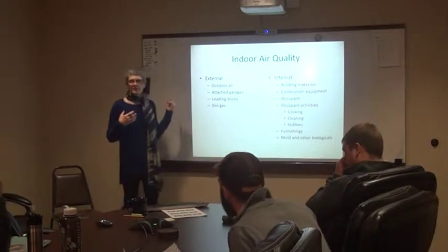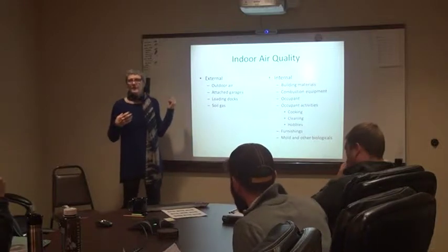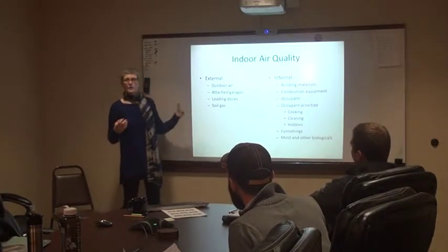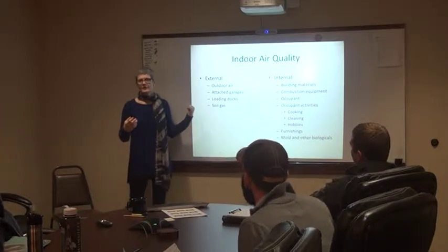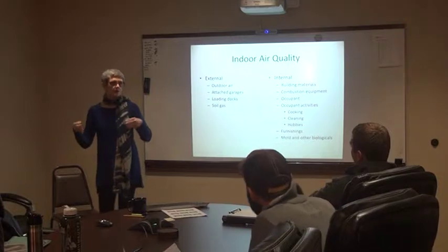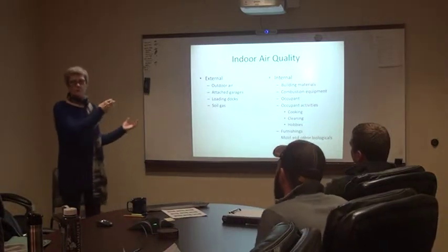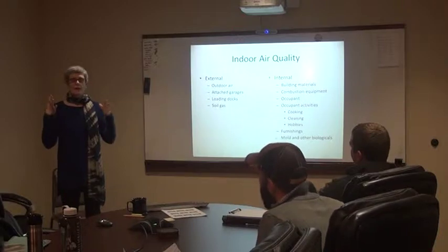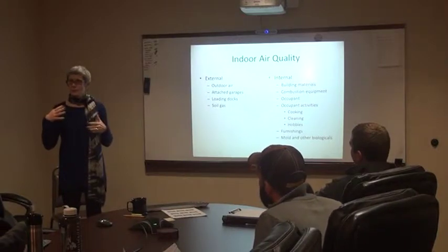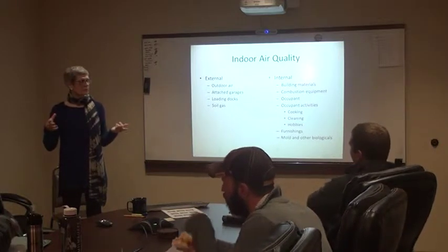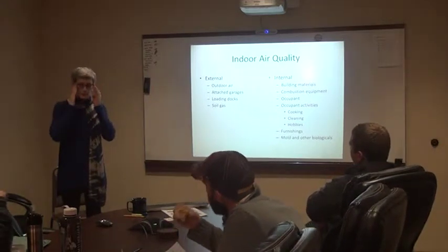And one of the things they found is that oftentimes these were designed so poorly that the intakes for the air would be close to the loading docks. So the diesel trucks and all the things that were unloading there, that was where the fresh air was coming from. So they're measuring things. Now I think architects and engineers are more aware of that kind of thing, so they make sure that doesn't happen.